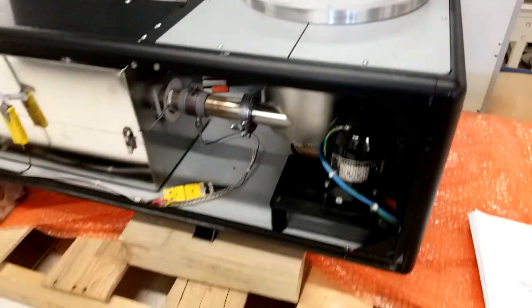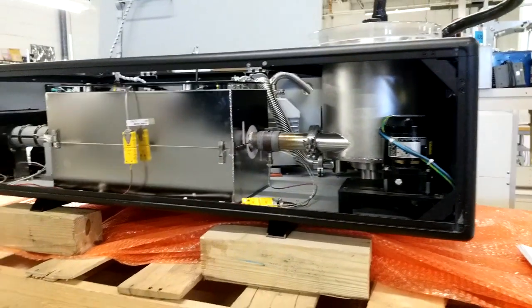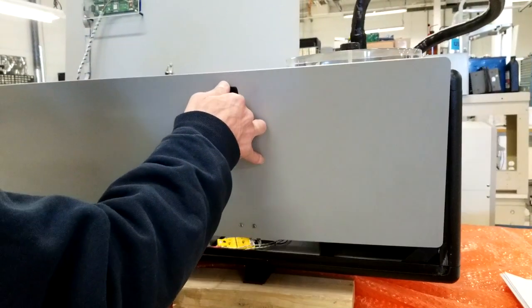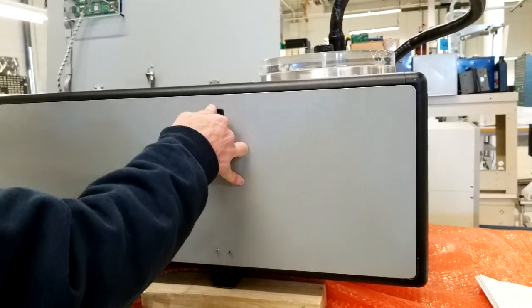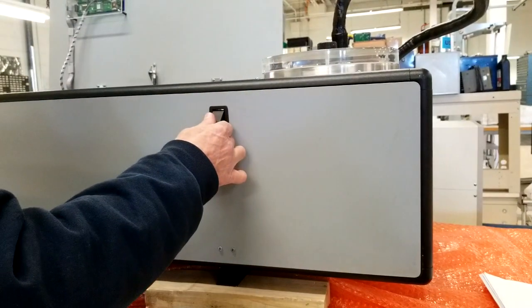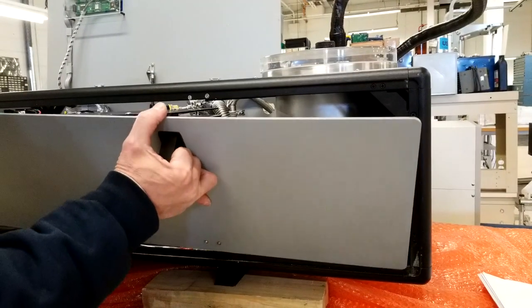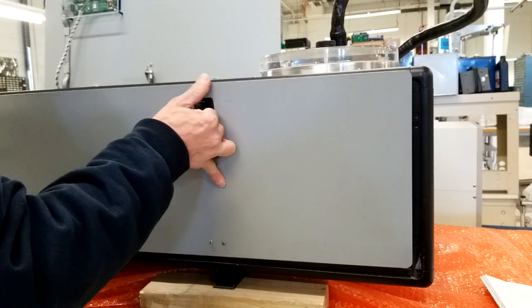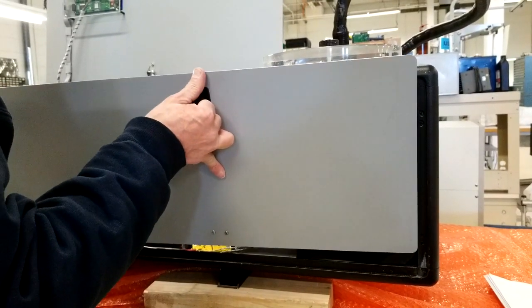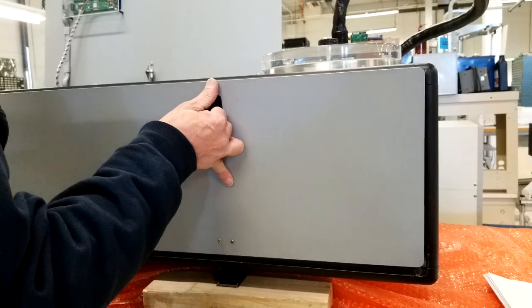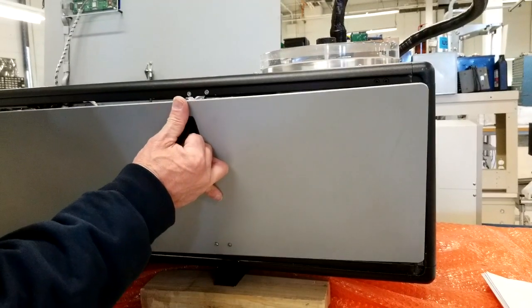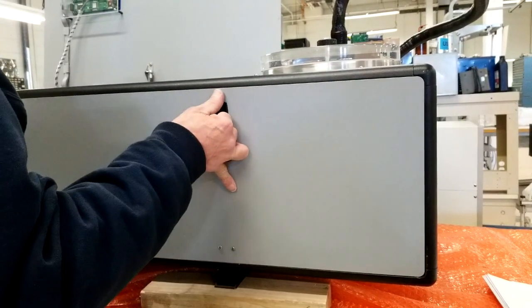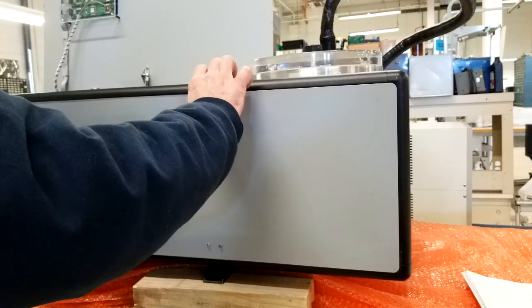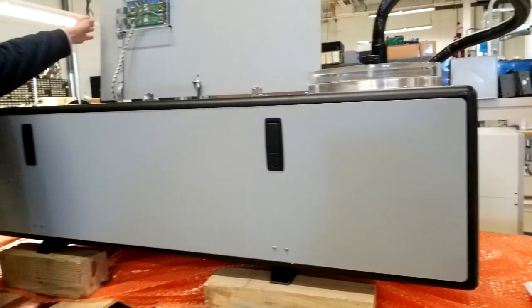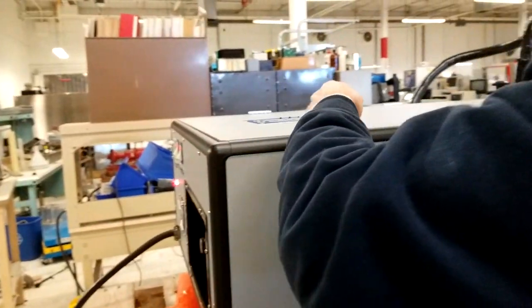Okay, so it's recommended, as you've seen in that recipe, that you need to be at least below 15 microns. It may take a while to get down to that point, depending on what you loaded in here, because of your load. So typically you'll load everything up, turn your cold probe on, and load your dimer and the vaporizer. And then allow it to pump down to below 15. Recommended.